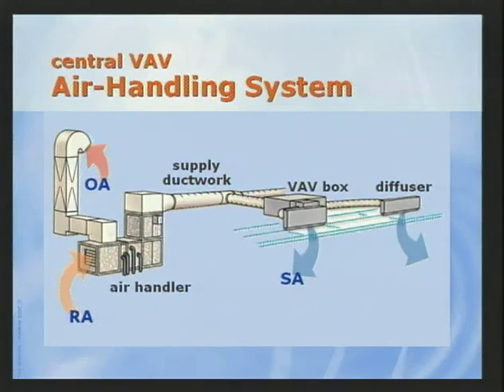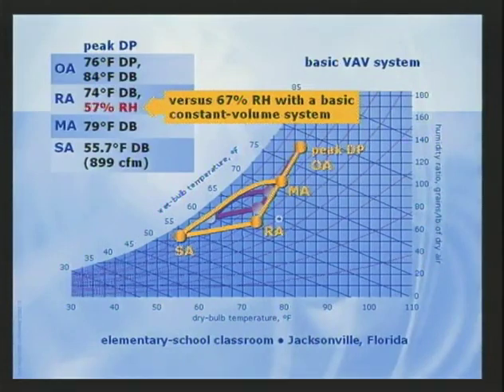Now, the third system type consists of a centralized air handler and multiple VAV terminals. The VAV terminal serving each classroom modulates the volume of supply air to match the changing load in the space. Meanwhile, the central supply fan delivers only the quantity of air needed at a constant supply air temperature. As the sensible cooling load in the space decreases, this VAV system reduces supply airflow to the space. Because the supply air is still cool and dry, the relative humidity in the classroom only rises to 57% at this example part load condition, compared to 67% with the basic constant volume system.